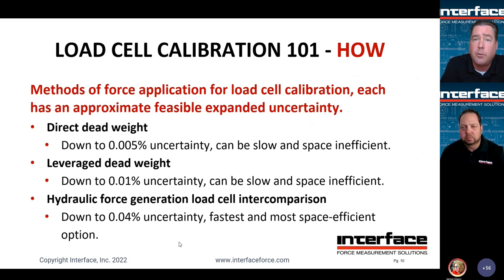How do we calibrate load cells and torque transducers? There are a couple different methods of force application for these calibrations. Number one is to use a direct dead weight. You can do this with hand weights or known masses or specifically built dead weight stands. These offer the lowest uncertainties, down to 0.005%. There are some trade-offs. It can be slow. It does take time for the weight stack to stabilize once the load is applied. And as you might imagine, it can be somewhat space inefficient in that you have a large amount of mass. It does take a large amount of room.